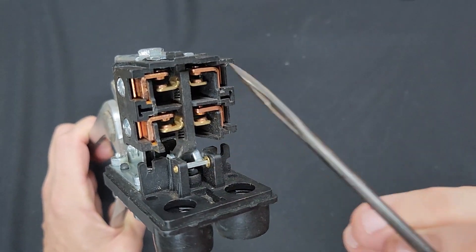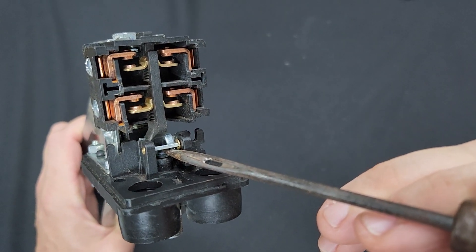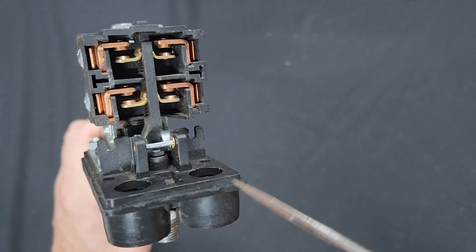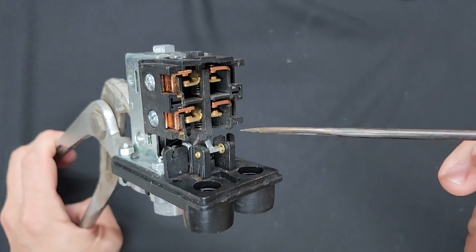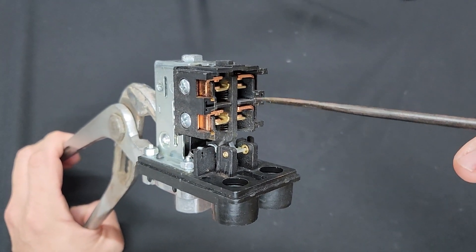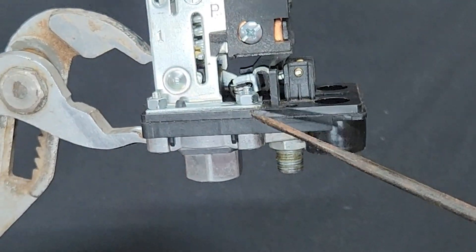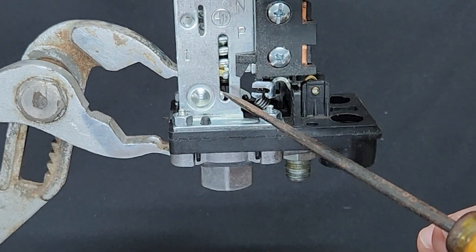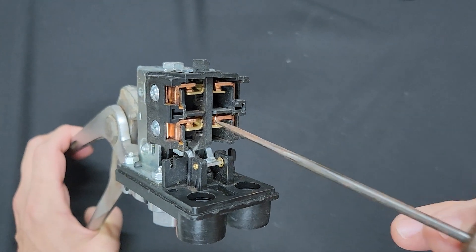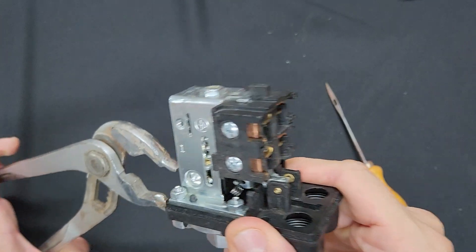So it comes up through the unloader valve when this is open. And while the compressor is switched off in this state, that's pushing down upon the needle of the unloader valve which allows an open vent, and so air escapes out through the unloader valve. And so when you start to use the air in your compressor tank, the pressure starts to reduce, reduce, reduce, reduce. As it gets less and less and less, this drops down, the spring pushes it back, re-engaging the contact points, and then the whole cycle commences again.